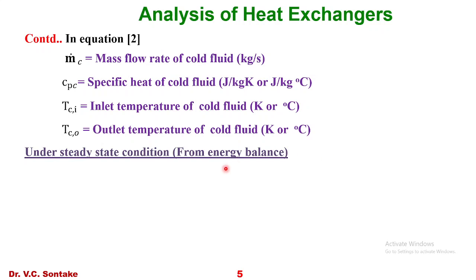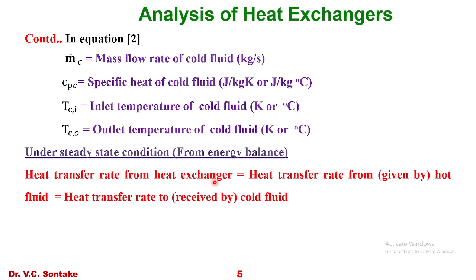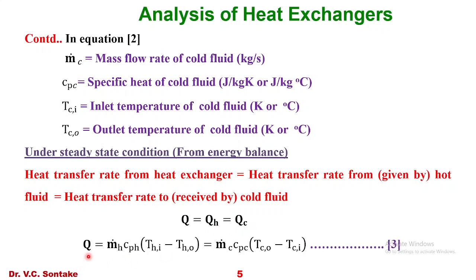Under steady state condition, the heat transfer rate given by the hot fluid and the heat transfer rate taken by the cold fluid will be the same. So, Q = Q_H = Q_C, meaning: Ṁ_H · C_PH · (T_HI − T_HO) = Ṁ_C · C_PC · (T_CO − T_CI). This is equation number 3 and is a very important relation obtained by energy balance under steady state heat transfer in a heat exchanger.